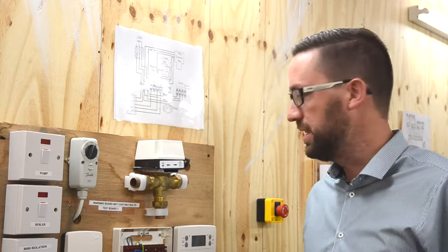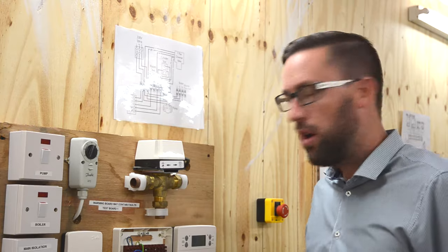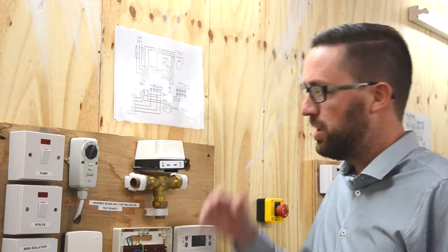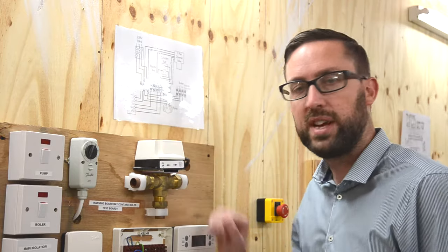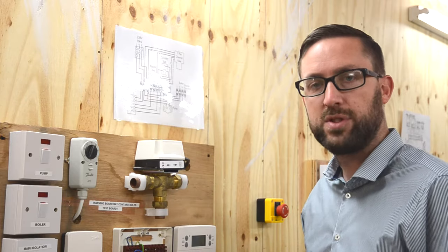Now what could happen is you could have a three-port valve like this in the airing cupboard. If you have one, over time the valve can get a lot of muck inside it. When the heating comes on, this motor has to motor the valve right the way open for the heating to work. Because of the muck, the motor is not powerful enough to open it right up.